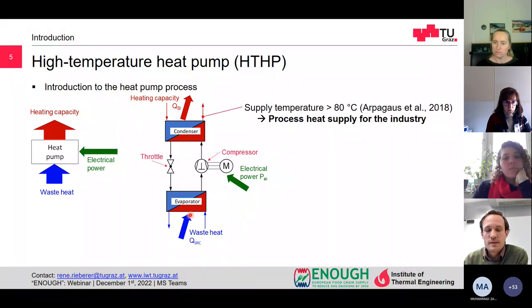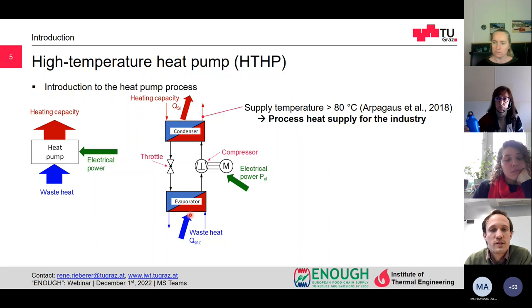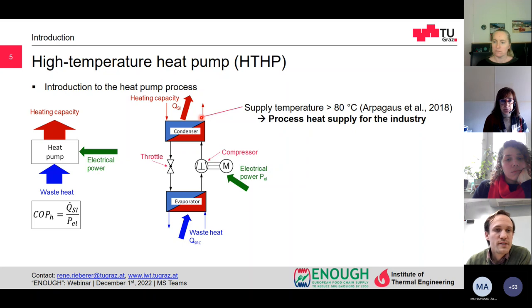For the high temperature heat pump, the definition is not so clear, but there are definitions of about 80 degrees Celsius or 100 degrees Celsius supply temperature, where it is called a high temperature heat pump. And this temperature is suitable to supply processes in the industry. The efficiency of such a heat pump is defined by the heating capacity divided by the electrical power input.